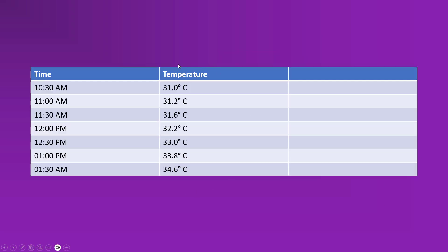Here you can see that the data logger is recording data against time. Our data is ambient temperature, shown in the second column, recorded against time — meaning at what time what was the ambient temperature. Our recording interval is about 30 minutes. The first reading was taken at 10:30 AM and the temperature was 31 degrees centigrade, and at 11 AM it was 31.2 degrees centigrade. In the same way, the data logger logs data against time.